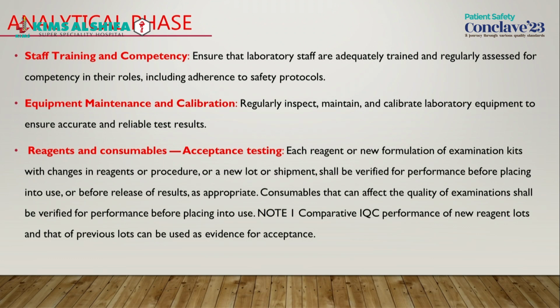So then comes the machine. All your ultra modern well equipped equipments which are in the process of analysis should be calibrated at least once in a year. They should be taken care of for preventive maintenance as per standard NABL. At least once in a year calibration should be done, and preventive maintenance. These two things are different.